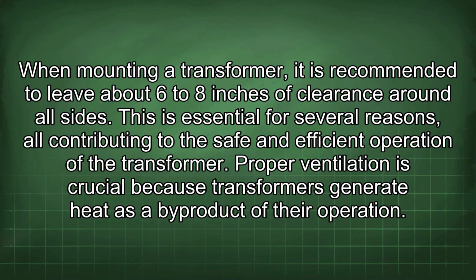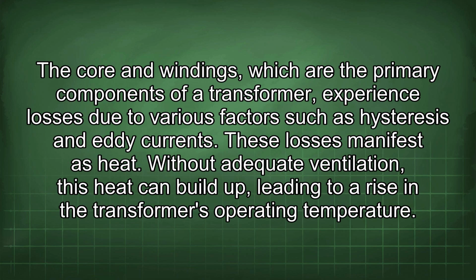When mounting a transformer, it is recommended to leave about 6 to 8 inches of clearance around all sides. This is essential for several reasons, all contributing to the safe and efficient operation of the transformer. Proper ventilation is crucial because transformers generate heat as a byproduct of their operation. The core and windings, which are the primary components of a transformer, experience losses due to various factors such as hysteresis and eddy currents. These losses manifest as heat.